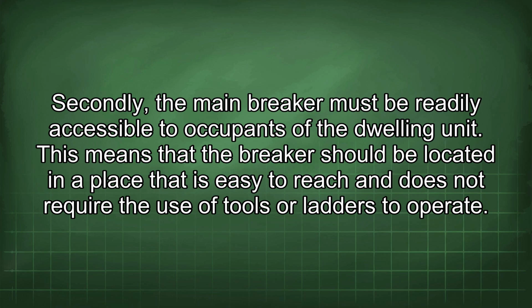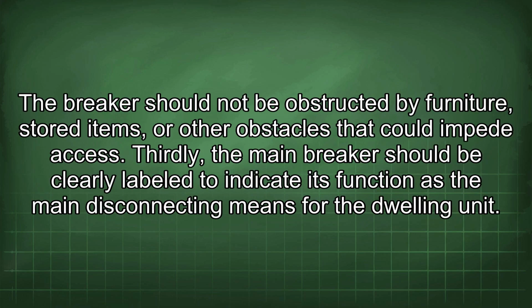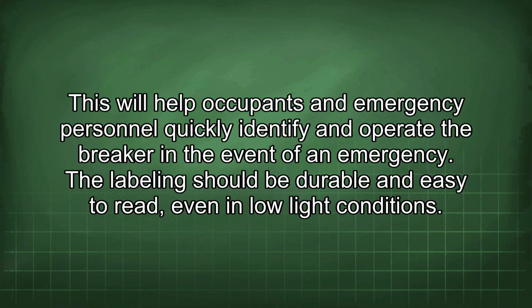Secondly, the main breaker must be readily accessible to occupants of the dwelling unit. This means that the breaker should be located in a place that is easy to reach and does not require the use of tools or ladders to operate. The breaker should not be obstructed by furniture, stored items, or other obstacles that could impede access. Thirdly, the main breaker should be clearly labeled to indicate its function as the main disconnecting means for the dwelling unit. This will help occupants and emergency personnel quickly identify and operate the breaker in the event of an emergency. The labeling should be durable and easy to read even in low light conditions.